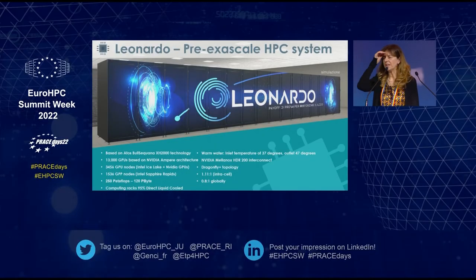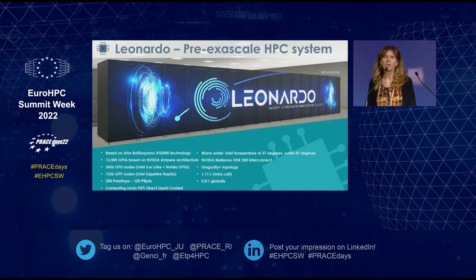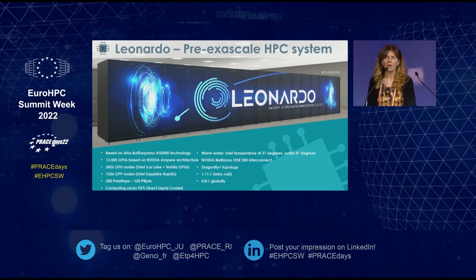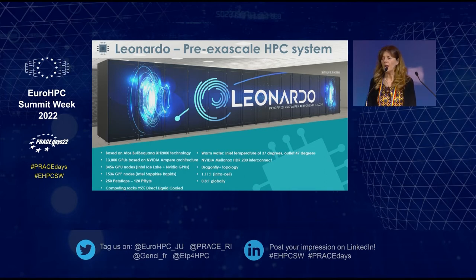Leonardo is one of the pre-exascale systems funded by EuroHPC and also by the Italian Ministry of University and Research. Leonardo is based on Atos BullSequana technology and contains over 13,000 GPUs based on NVIDIA Ampere architecture. The computing power we foresee is around 250 petaflops, with a storage of 120 petabytes. The cooling technology is 95% direct liquid cooling with warm water technology, and NVIDIA Mellanox interconnect of 200 gigabit per second will be used.